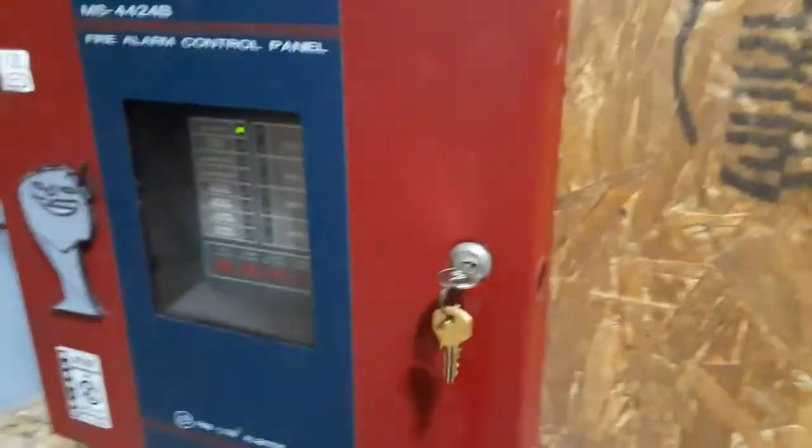So let's go with the notification appliance devices. This is my Wheelock RSS-MCW. Candela is set to 110 — I forgot to change the candela again. I was messing around with the system testing a few things and forgot to change it. It's supposed to be 15, but moving on.